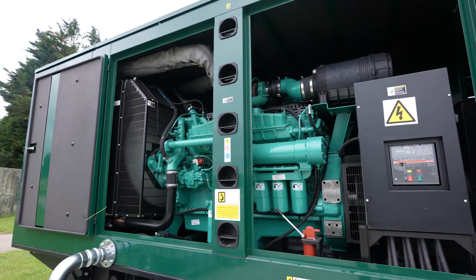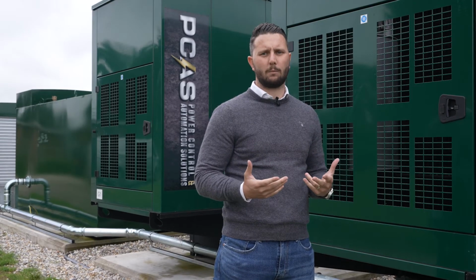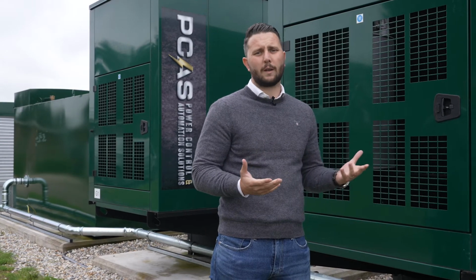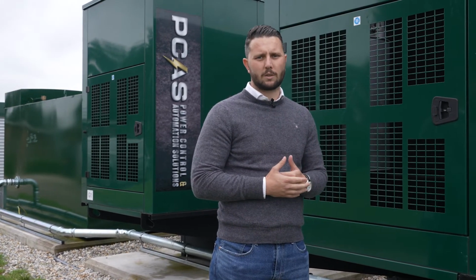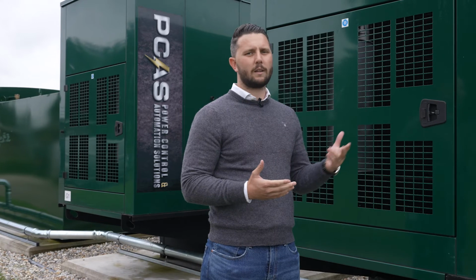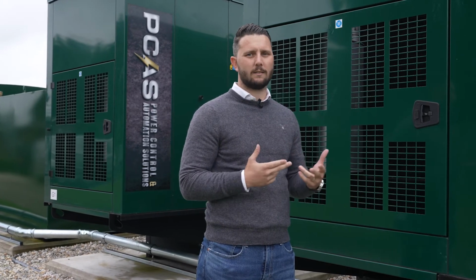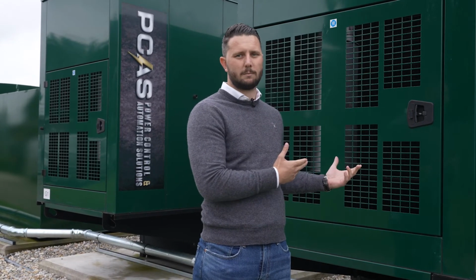The UPSs are always on, but they kick in when the grid feeds fail. They have a 20-minute runtime, and inside that 20 minutes there's a 30-second delay before the generation system kicks in.